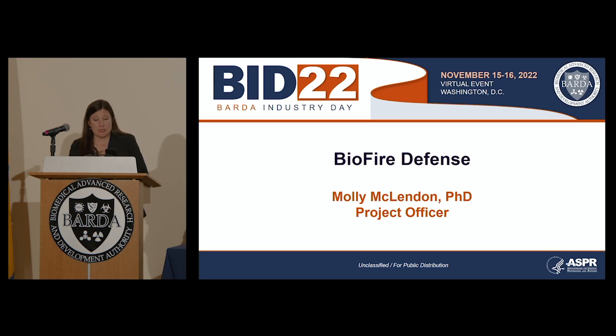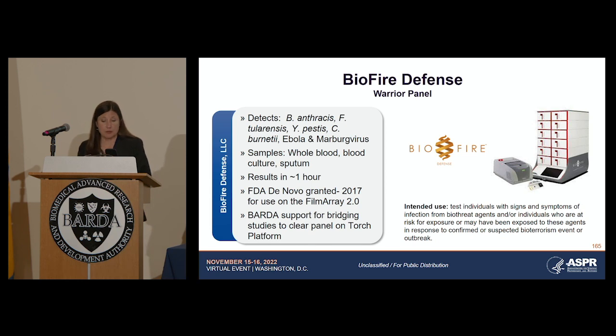A de novo request was granted by the FDA for the Warrior panel using whole blood specimens and blood cultures in early 2017, and the test received 510K clearance a few months later to use sputum samples. The panel is currently FDA cleared for use only by the Department of Defense and is run on the BioFire FilmArray 2.0 instrument. On the right side of this slide is the BioFire FilmArray torch system. This instrument is capable of higher throughput than the FilmArray 2.0 instrument because it can run up to 12 samples at a time. It is also randomly accessible.